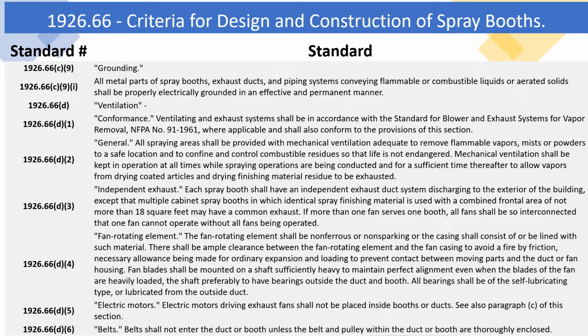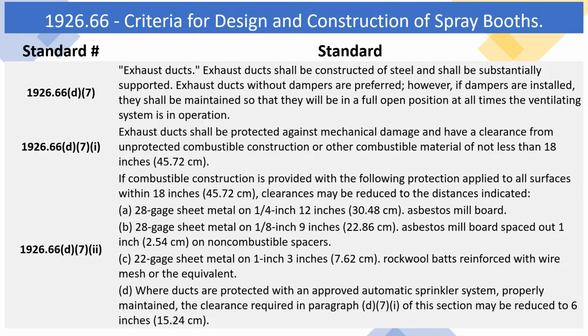1926.66(d)(5) Electric motors. Electric motors driving exhaust fans shall not be placed inside booths or ducts. See also paragraph (c) of this section. 1926.66(d)(6) Belts. Belts shall not enter the duct or booth unless the belt and pulley within the duct or booth are thoroughly enclosed. 1926.66(d)(7) Exhaust ducts. Exhaust ducts shall be constructed of steel and shall be substantially supported. Exhaust ducts without dampers are preferred, however. If dampers are installed, they shall be maintained so that they will be in a full open position at all times the ventilating system is in operation.